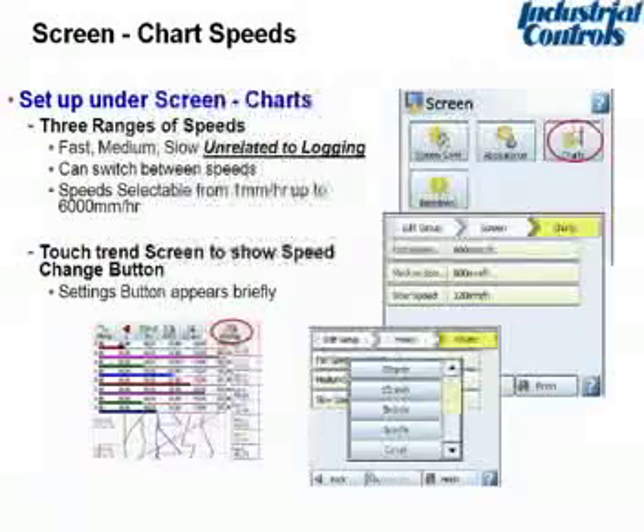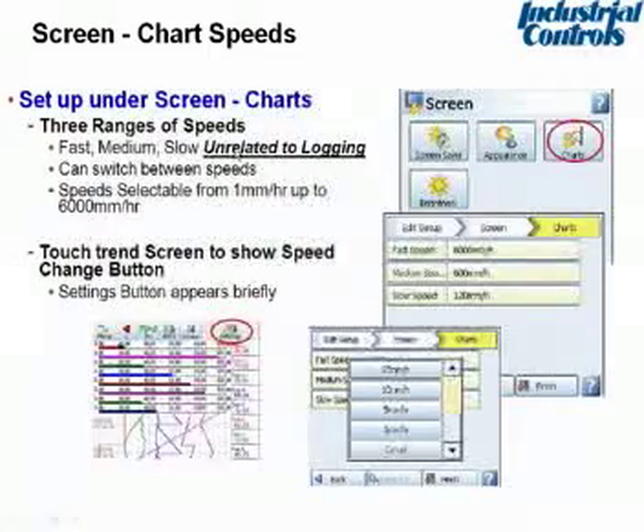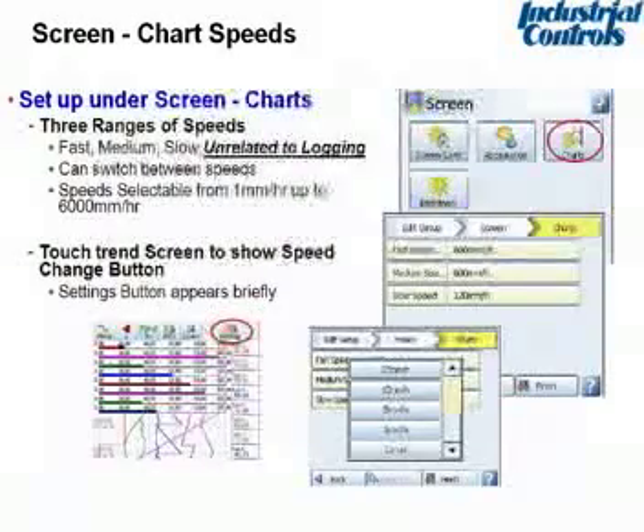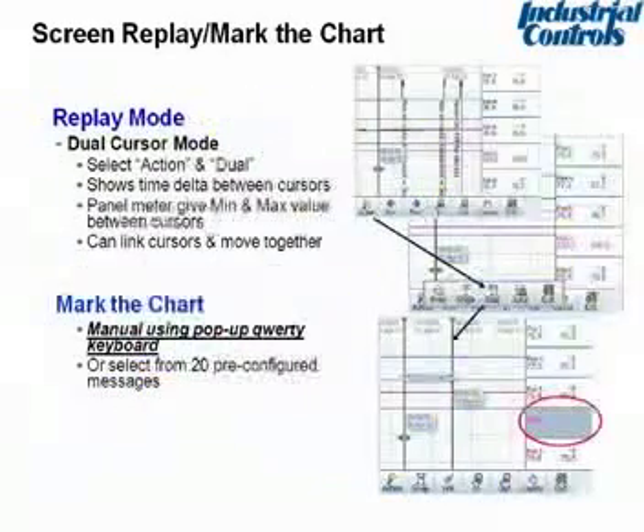Chart speeds. We can change chart speeds like you can on a paper recorder, from the front of the screen. One of the most important things to recognize is that the chart speed is not related to the logging or the capture of the data. So what most people do on the trend is they pick a chart speed that gives you the history of the chart for the time period that you want the operators to see. You know, the last 2 hours, last 8 hours, last 24 hours. And these are all configurable to chart speeds.